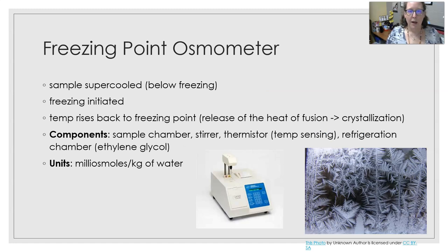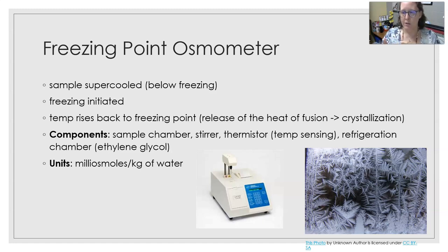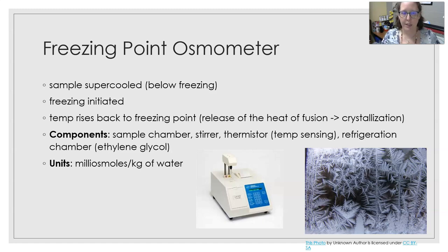The freezing point osmometer works as follows: first, the sample is supercooled — cooled below its freezing point. Then freezing is initiated by a small stirrer; as soon as it vibrates and moves, crystals form. As the crystals form, the temperature rises back to the freezing point and settles there, due to the release of the heat of fusion, which causes crystallization. The components of a freezing point osmometer are the sample chamber, the stirrer, the thermistor (which senses the temperature), and the refrigeration chamber, which contains ethylene glycol to supercool the sample. The result is reported in milliosmoles per kilogram of water.